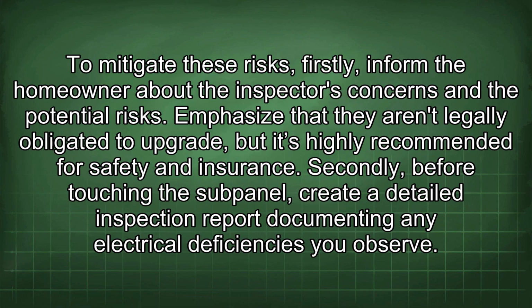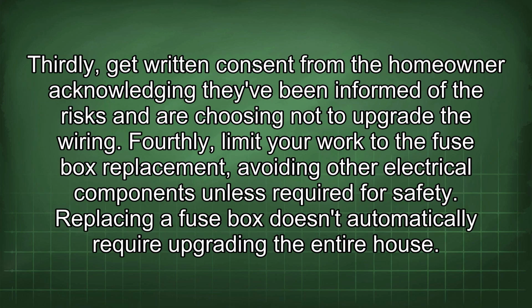To mitigate these risks, firstly, inform the homeowner about the inspector's concerns and the potential risks. Emphasize that they aren't legally obligated to upgrade, but it's highly recommended for safety and insurance. Secondly, before touching the subpanel, create a detailed inspection report documenting any electrical deficiencies you observe. Thirdly, get written consent from the homeowner acknowledging they've been informed of the risks and are choosing not to upgrade the wiring. Fourthly, limit your work to the fuse box replacement, avoiding other electrical components unless required for safety.